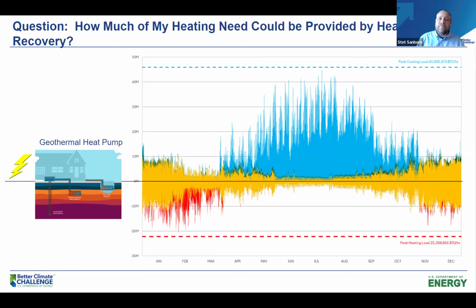One of the key things that folks don't often realize is that when you pick a heat pump that's a geothermal-based heat pump, the heat pump is often smaller, has a lower connected load on the electrical side than what you would need for an air source heat pump to deliver the same amount of heat. And so again, if you're working within the limits of an existing electrical system, a geothermal-based heat pump actually might fit in really nicely, be able to meet the entirety of your load without necessarily upgrading the electrical service for the entire building. So again, these are strategies that you're going to want to ask your auditor.